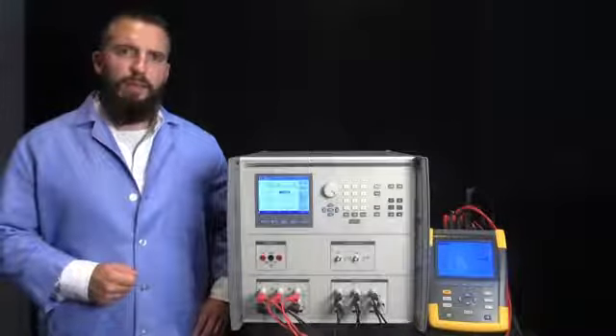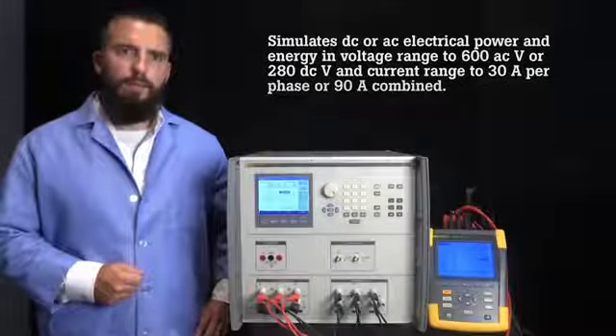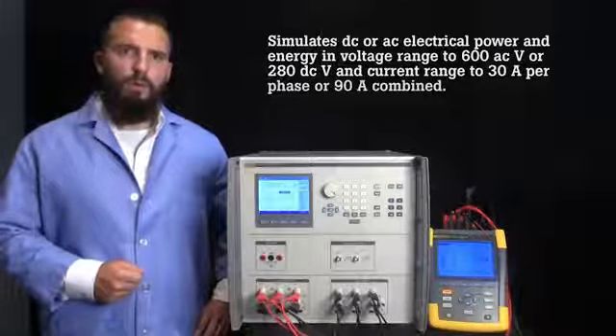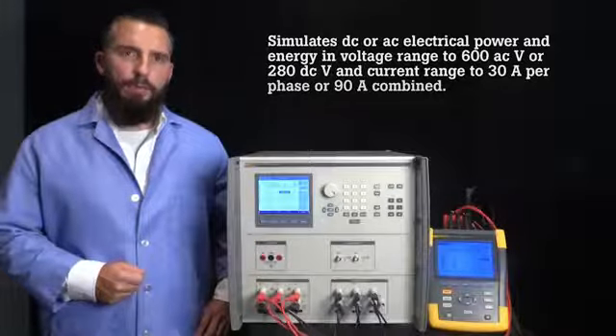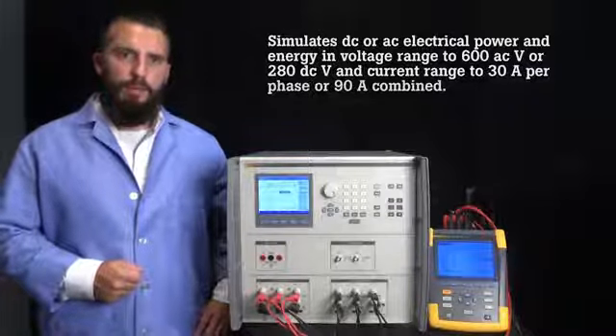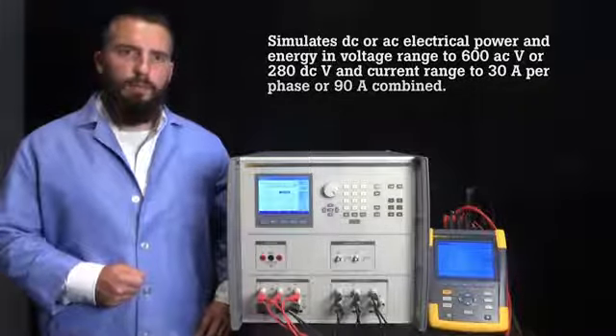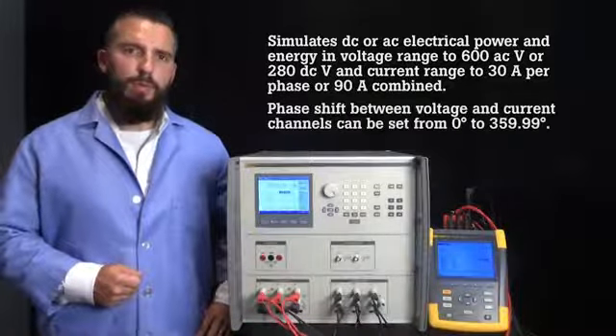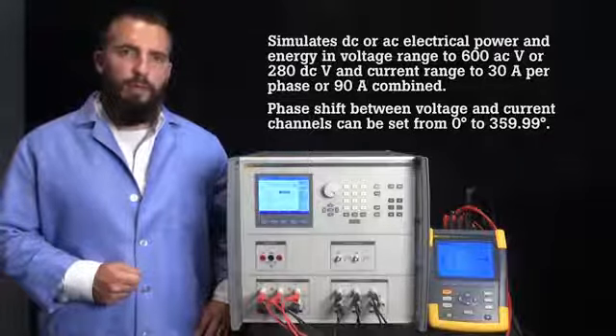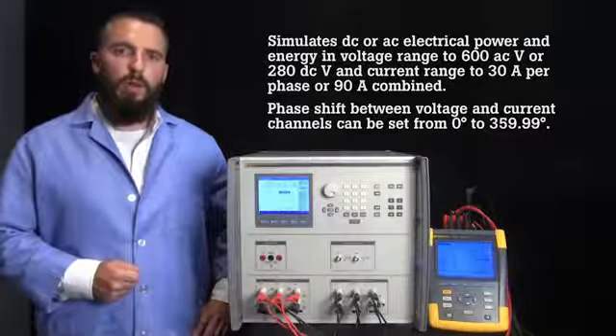The 6003A simulates DC or AC electrical power and energy in voltage ranges from 1 volt to 600 AC volts or 280 DC volts and current ranges from 8 milliamps to 30 amps per phase or 90 amps combined into one phase. Phase shift between voltage and current channels can be set from 0 degrees to 359.99 degrees with the best accuracy of 0.01 degree.